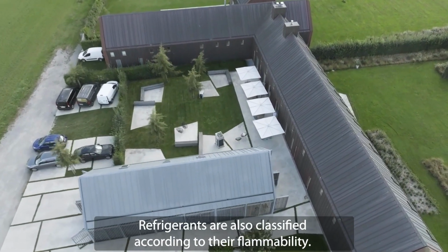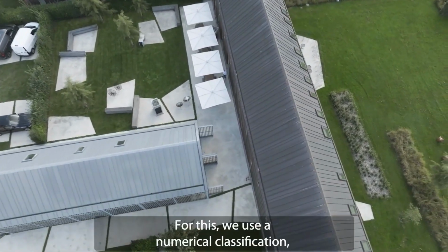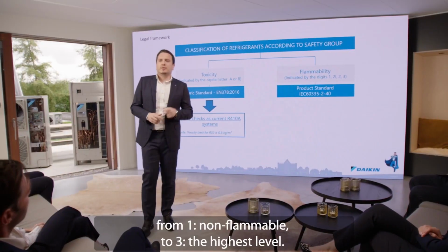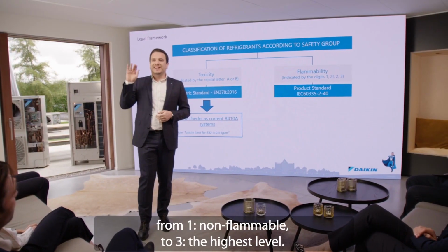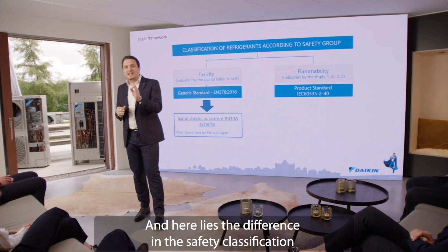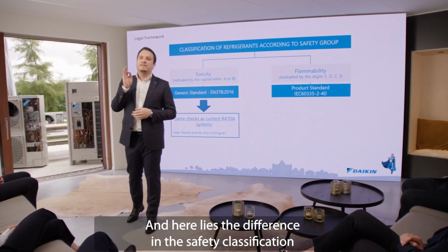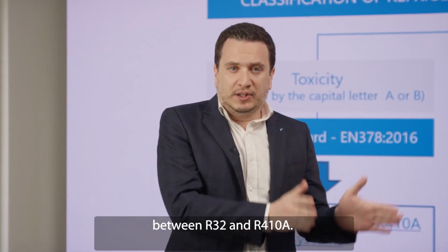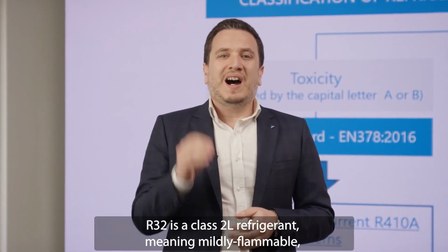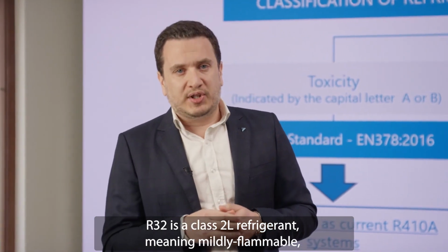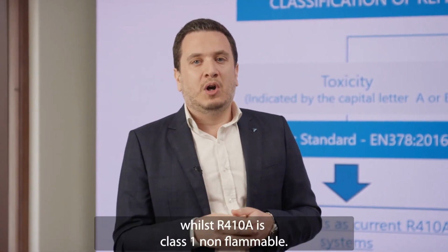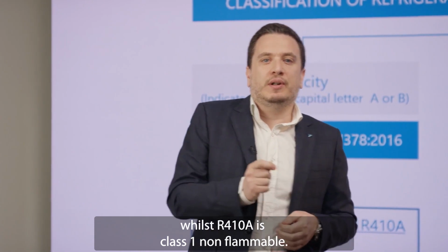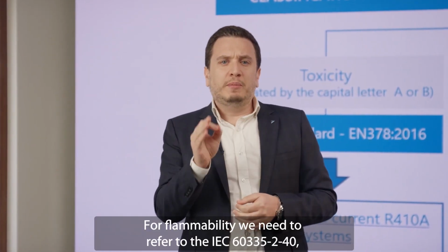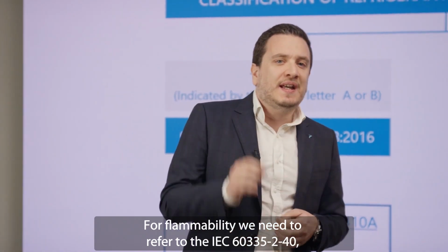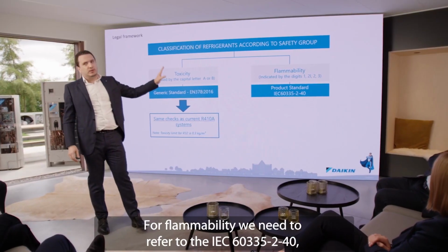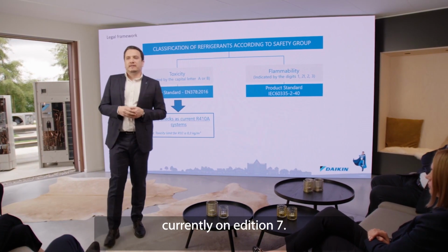Refrigerants are also classified according to their flammability. And for this, we use numerical classifications from 1, non-flammable, to 3, the highest level. And here lies the biggest difference regarding safety classification group between R32 and R410A. R32 is a class 2L refrigerant, meaning mildly flammable, whilst R410A is class 1, non-flammable. For flammability, we need to refer to the IEC 60335-2-40, currently on edition 7. Why?